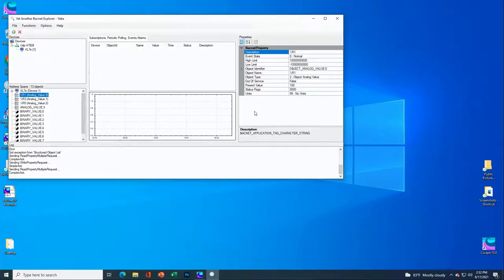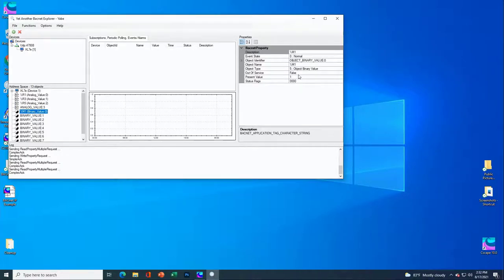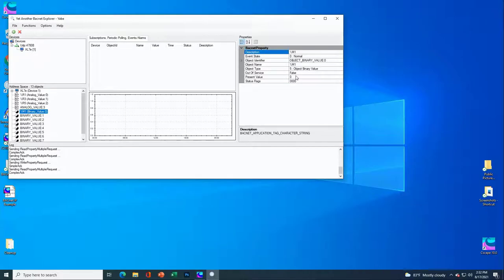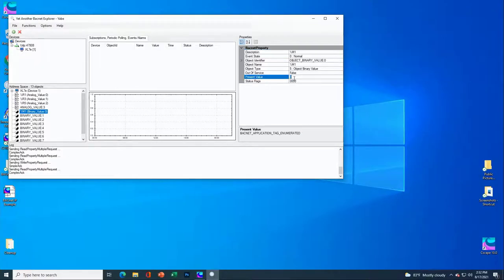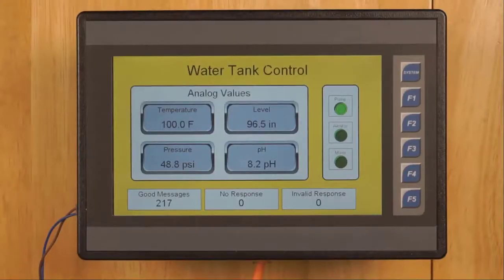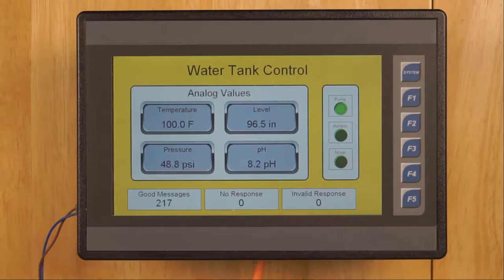Going back to Yabe, let's look at one of our binary values. The first binary value currently has a present value of one. We can go ahead and change that — and now going back to look at our OCS, that first output labeled 'pump' is now off. Going back into Yabe, we have the ability to change it again, and back to the OCS — sure enough, we were able to turn the pump on and off from Yabe. Yabe isn't the only utility available; there are a variety of other utilities in the market, some free and some paid.